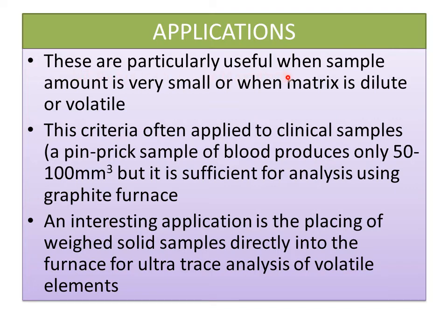Electrothermal atomizers are particularly useful when the sample amount is very small or when the matrix is dilute or volatile. This applies especially to clinical samples — a pinprick blood sample of only 50 to 100 cubic millimeters is sufficient for complete analysis using a graphite furnace. Another interesting application is placing small solid samples directly into the furnace for ultra-trace analysis of volatile elements.